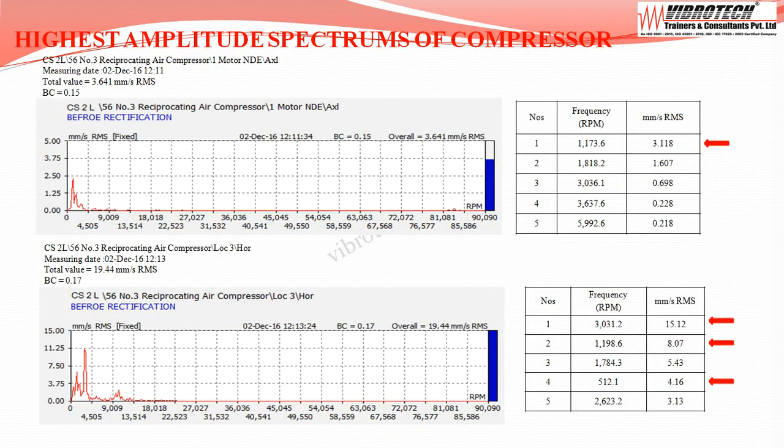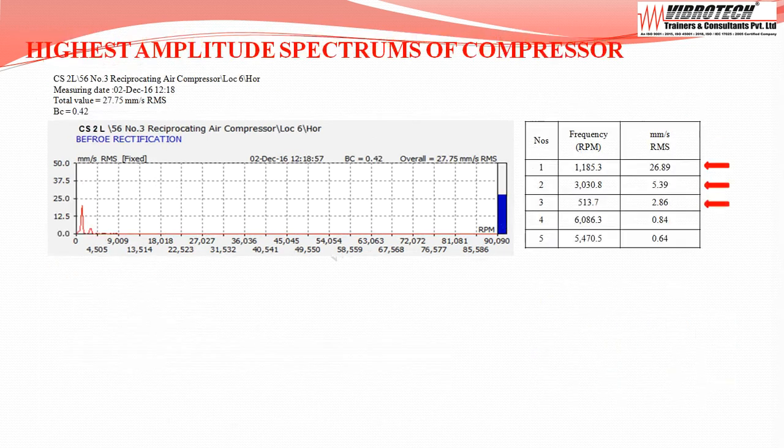Going through the spectrum and frequencies of the compressor: the dominant peak frequencies at motor non-drive end are 1x the running rpm of the compressor. The spectrum at pulley free end bearing shows dominant peak frequency at 2x running rpm, along with sub-harmonics, indicating improper rigidity of the base frame. The dominant peak frequencies at the low pressure cylinder are 1x and 3x the running rpm, with sub-harmonics generated due to improper rigidity at pulley free end bearing also indicated.